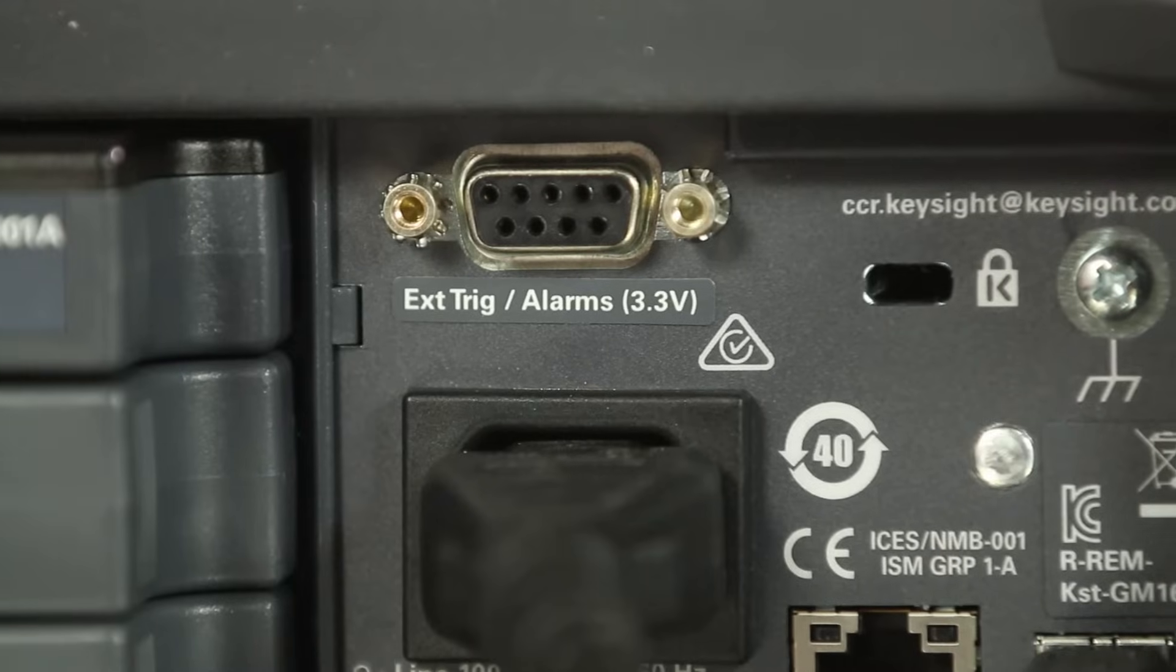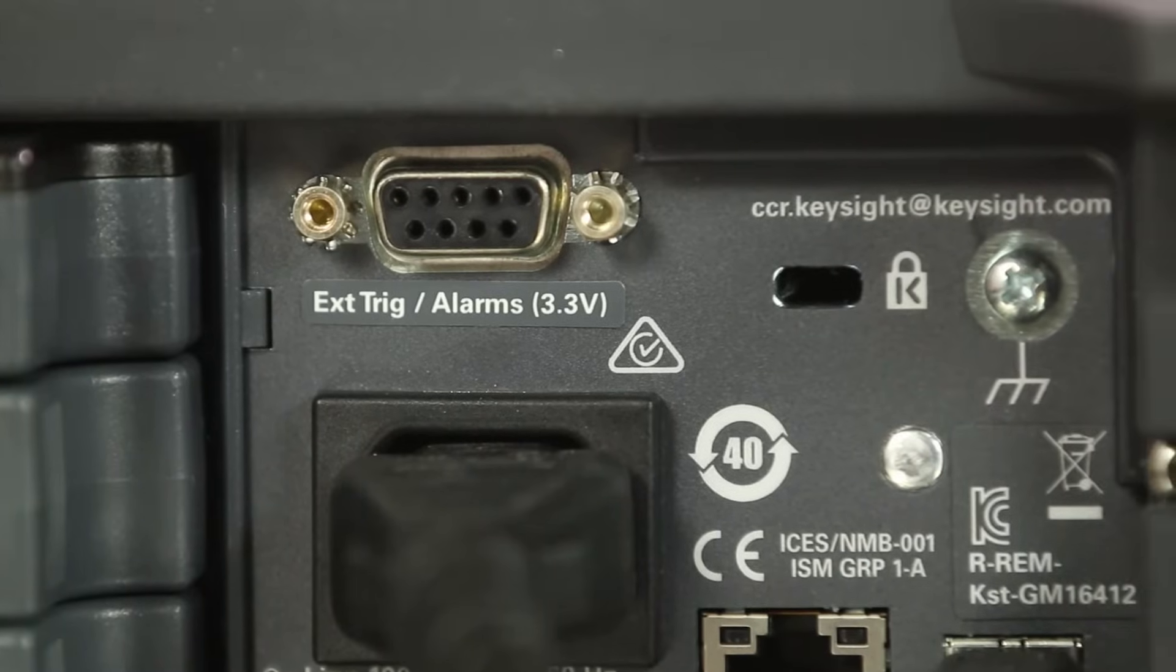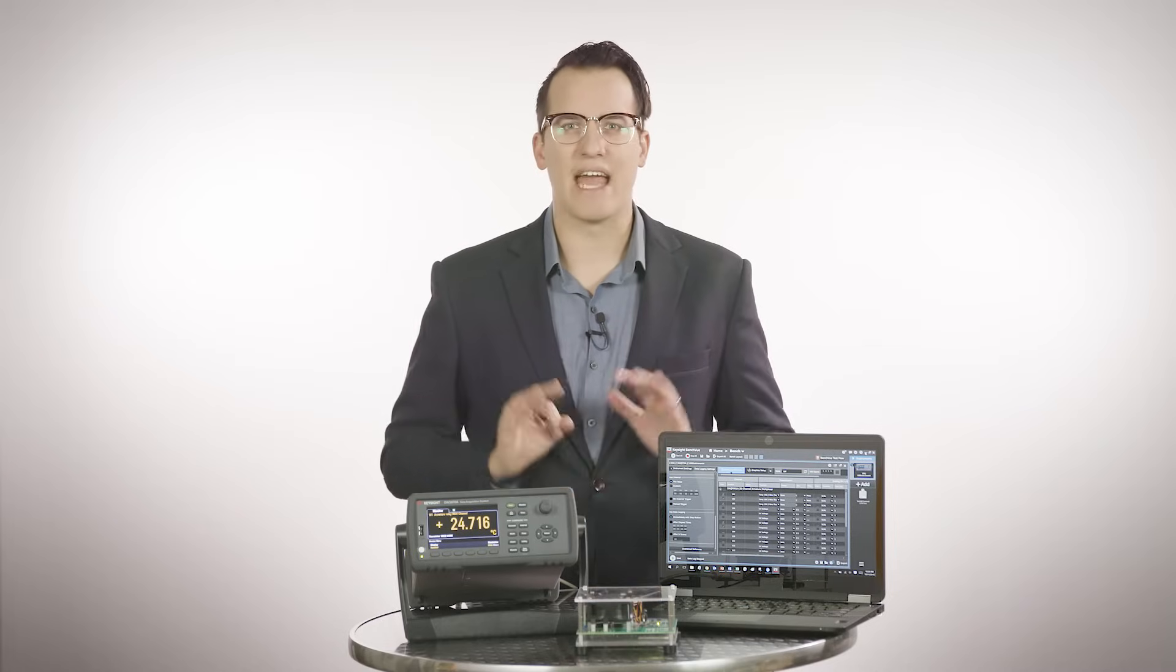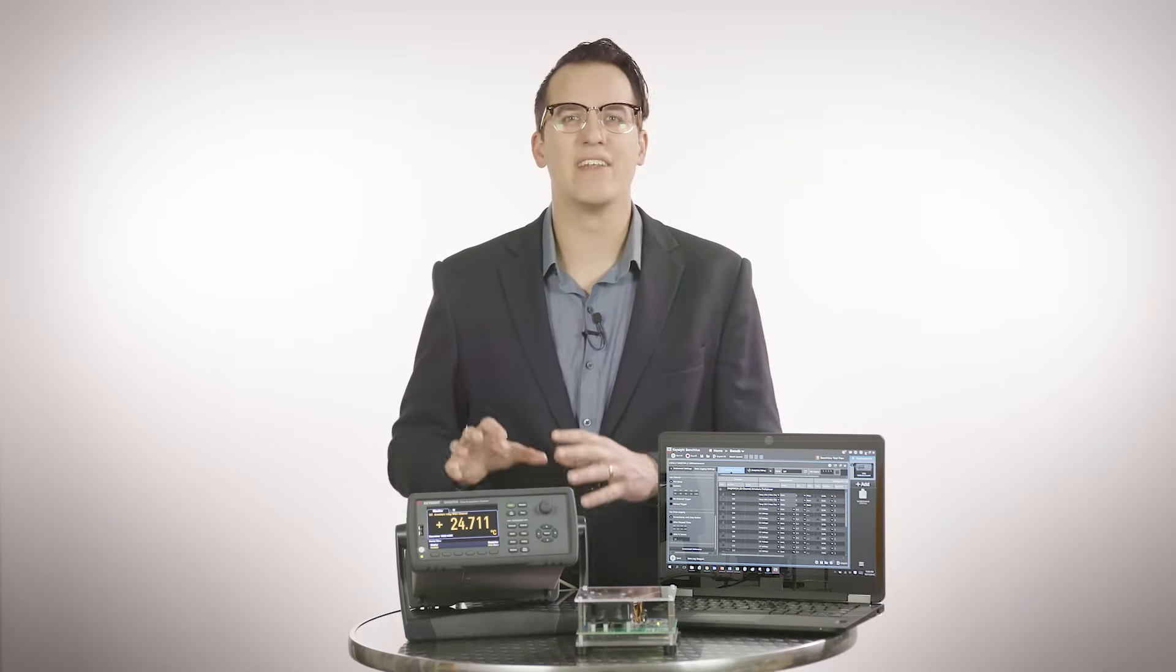Another useful feature is the alarm system in the DAQ. You can set TTL alarm output to trigger external alarm lights, sirens, or to a control system that will take corrective actions.